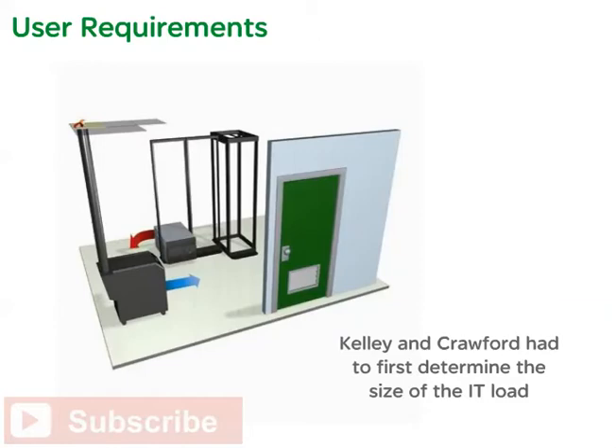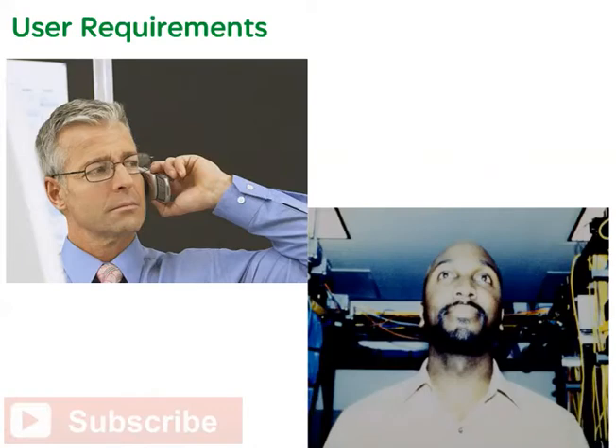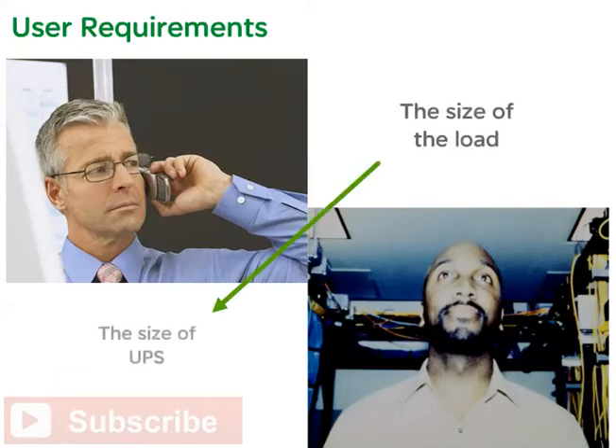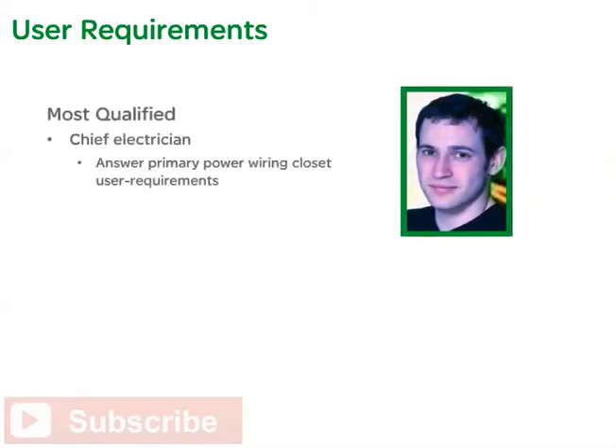In order to determine how much cooling was needed for the new wiring closets, Kelly and Crawford first had to determine the size of the IT load. These figures allowed Crawford to properly size the power and cooling required for the room. The size of the load helped determine the size of the UPS required. By calculating the UPS size and considering amounts of solar gain, lights, fans, and other heat sources, Crawford determined how much cooling was needed for each of the five wiring closets. Jason Stewart, Acme's chief electrician, was deemed the most qualified person to address primary power, UPS, and PDU wiring closet user requirements.